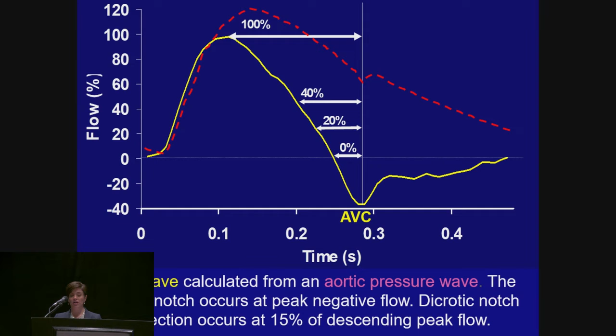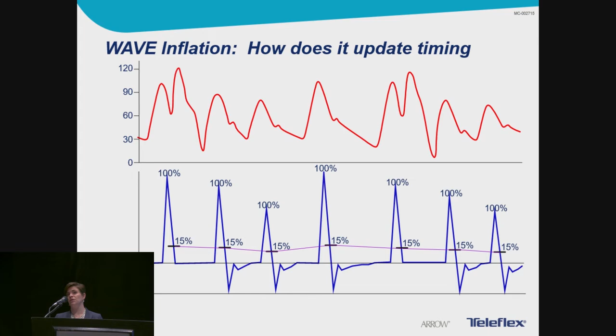A question that we get a lot of times is, how do you update your timing with this? Well, this shows how timing is set and adjusted within the beat as each beat occurs. WAVE calculates flow where peak flow is relative to peak pressure, and timing is then set when the descending flow point reaches 15% after peak flow. Since each peak flow is relative to peak pressure, the 15% point varies with each beat. Hence, timing is set for each beat specifically as that beat occurs. So it is truly an intra-beat timing, and it only looks at that cardiac cycle that it's working with because it's looking at the flow of that single cycle.